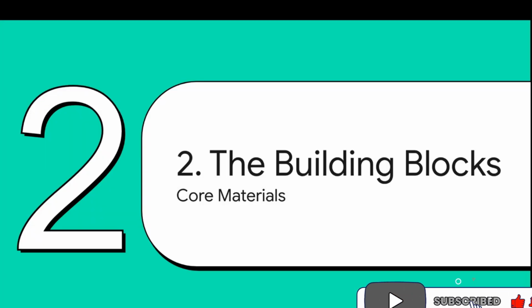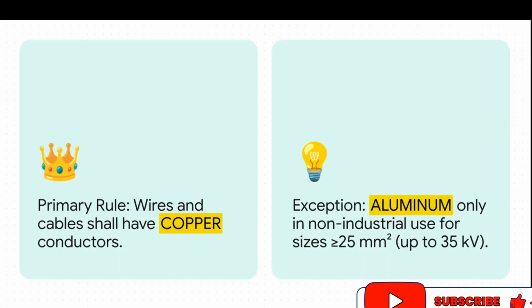All right, next up, let's talk about the building blocks. These are the non-negotiable rules about materials that you have to have down cold before you even think about starting a project. And here is rule number 1, and it is crystal clear. Copper is king. The standard says wires and cables shall have copper conductors. Full stop. Now, there is one very narrow exception. You can use aluminum, but, and this is a big but, only in non-industrial settings and only for bigger cables.